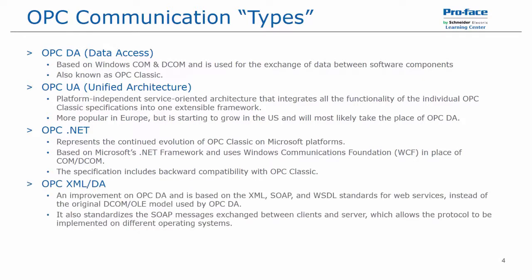And then there's OPC XML-DA. It's an improvement on the OPC DA standard and is based on the XML SOAP and Web Services Description Language, or WSDL, standards for web services, instead of the original DCOM or OLE model used by OPC Classic. It also standardizes the SOAP messages exchanged between clients and servers, which allows the protocol to be implemented on different operating systems.